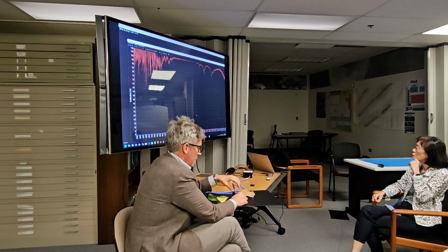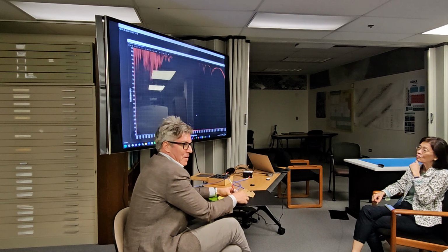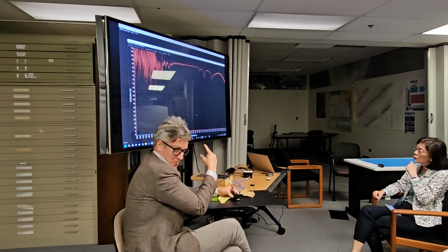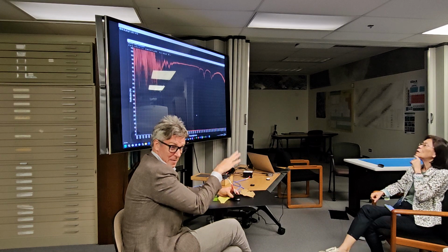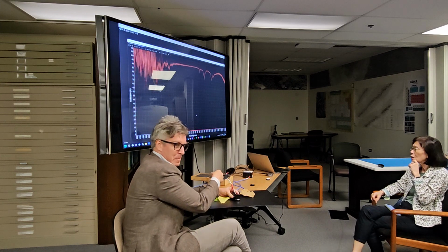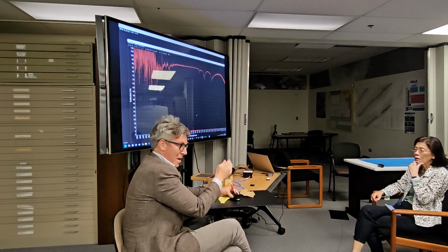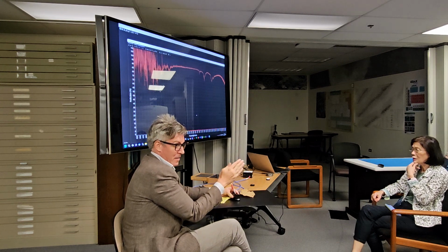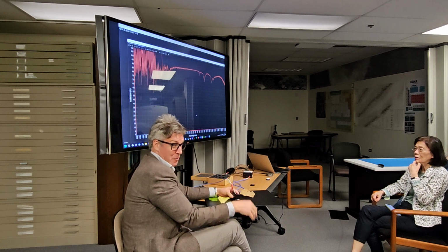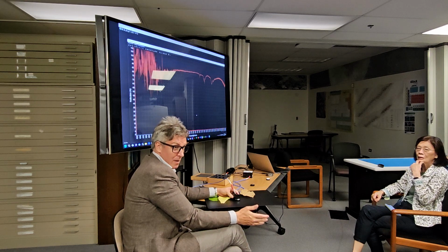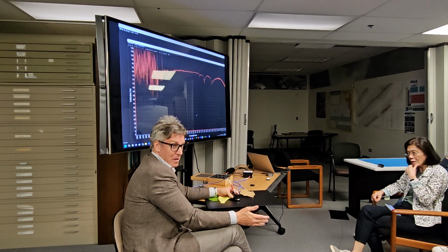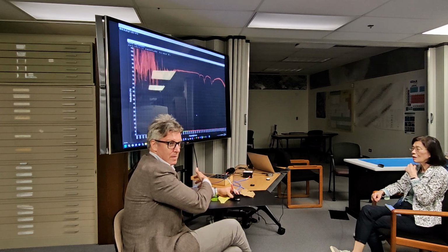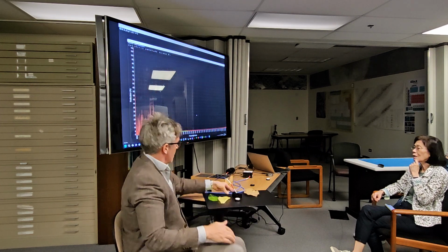So based on its chemical composition and the calibration of this before they shipped it to me, I know exactly what wavelength those absorption troughs are supposed to take place in, right? So if I build a spectrometer and I compare my measurement with the reference and the troughs are at different spectral locations, different wavelengths, then I know my spectrometer isn't working right. And I've got an offset in the wavelength calibration, which I can then try and fix. Okay.